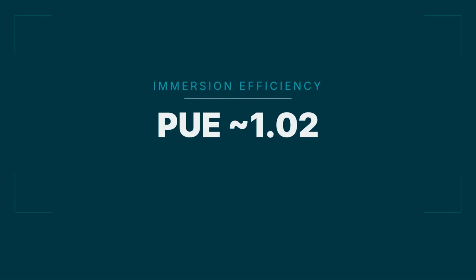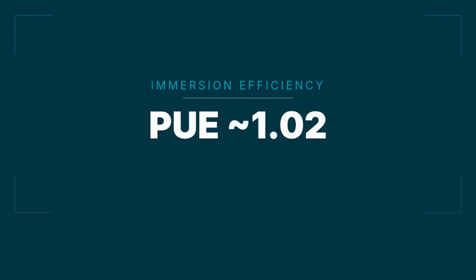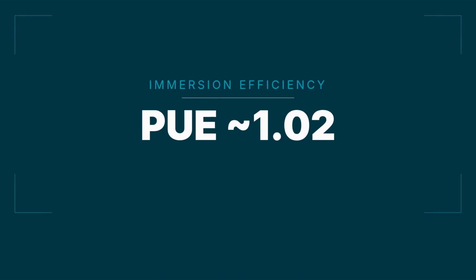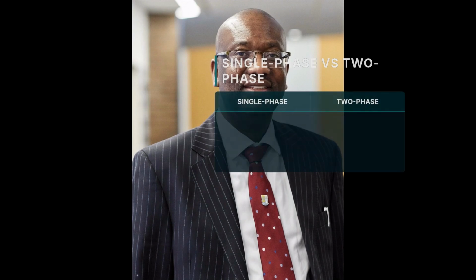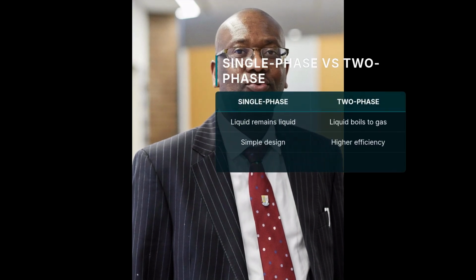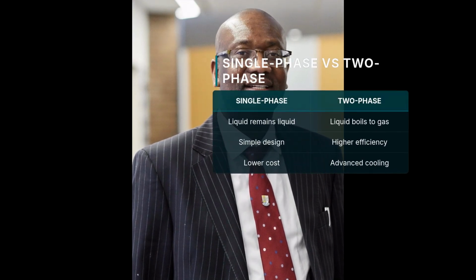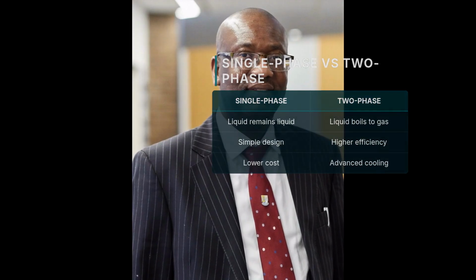Cooled fluid then returns to the tank. No fans are required. Servers run completely fanless in immersion. This efficiency drives the power usage effectiveness down toward a theoretical minimum of 1.02. To understand this further, we must look at the two primary types of immersion: single-phase and two-phase.